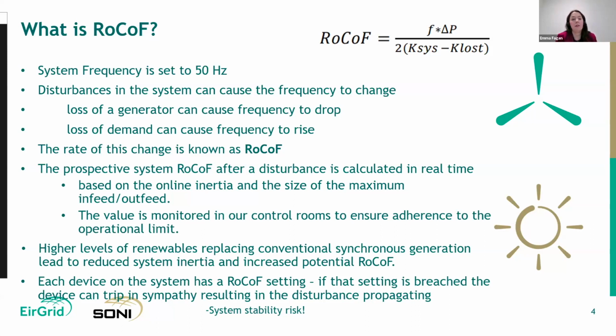Prospective RoCoFs in the system after a disturbance are calculated in real time in our control rooms. This is a calculation based on the online inertia and the size of the maximum in-feed or out-feed. And we monitor this value all the time in our control rooms to ensure adherence to the operational limit. So we're constantly considering contingencies that might lead to a frequency change, and we would consider what the RoCoF would be as part of that.